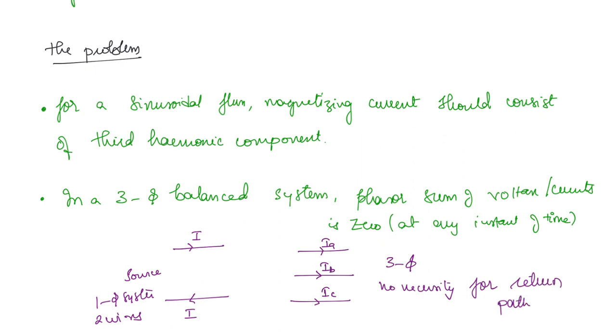Now what is going to happen in a 3-phase transformer? The third harmonic components of the magnetizing current should flow so that sinusoidal flux is maintained. Flux is sinusoidal. Now the third harmonic components are all going to be in phase, right? That's what we have discussed. Now when all the third harmonic components are in phase, then there will be a necessity for a return path. In a normal 3-phase system, because we are not concerned with the third harmonic components, we are not concerned with the return path. But in 3-phase transformers, since the third harmonic current is necessary for a sinusoidal flux, we will need a return path wherein the third harmonic currents can flow.